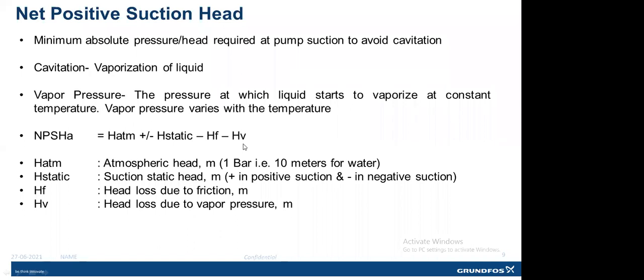And head loss due to vapor is calculated with reference to the temperature of the liquid. So always make sure, if NPSH available at site is lesser than the NPSH required, we need to take into account the pipeline size, or we can say the water level. If it is lesser than NPSH required, we can vary only two factors, that is frictional loss or static head. We'll check whether it is possible to increase the static head. For example, we are taking water from a tank. Is it possible to increase the water level in the tank?